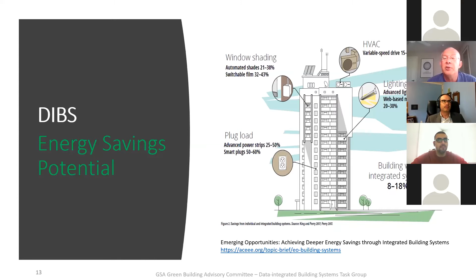ACEEE has an initiative for about a decade called Intelligent Efficiency, which looks at the smart functionality of systems in their own right and when connected together. A combination of plug load, window shading, HVAC, and lighting controls can deliver somewhere between 8 and 18% additional energy savings through these integrated systems. That's a significant amount of energy enabled through connected building systems.